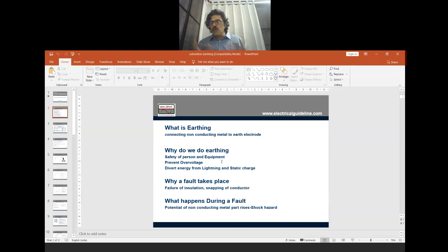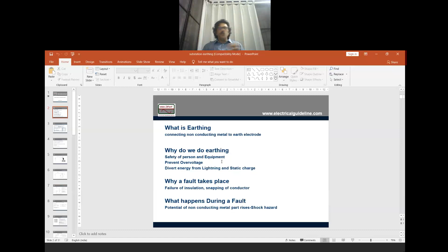Now, why do we do earthing? Always two reasons: human safety and equipment safety. When I say equipment safety, it is about voltage. We don't want a huge over voltage. You may ask, why, if I don't earth, will there be a huge over voltage? When I say equipment safety, it is about neutral earthing. If I don't earth the neutral, it can lead to a very large over voltage.